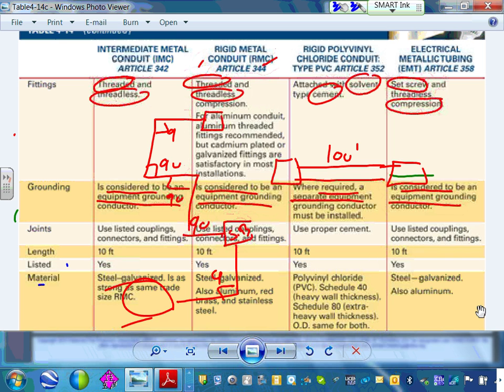Now here's another restriction. If you're using it just as a ground, there are also other restrictions. I can't remember exactly, but EMT conduit, for example, I think after 200 feet, it becomes ineffective as an equipment ground conductor. So what do you need to do? You have to pull an equipment ground conductor inside. There's a table, I'll share it with you, it's not in any secret book, where there's a limitation on how far you can pull a conduit and still have an effective equipment ground conductor.